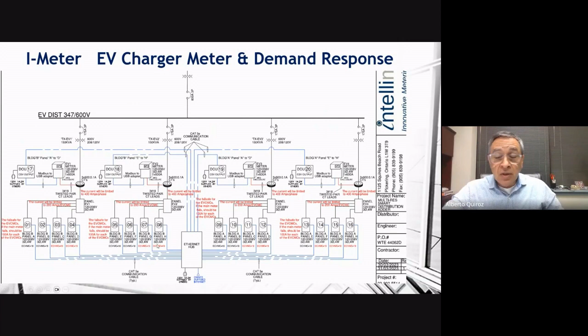That red line is your capacity, the capacity available for charging. Because the EVCMC lets you install more chargers than the capacity, if you didn't have anything to manage that capacity, the blue line, the theoretical consumption, would exceed that limit. At point A it would go beyond that limit, and that would either overheat the transformer, overheat the feeder, trip the breaker, or blow a fuse. So the system looks at that limit and tracks the consumption to make sure that never happens.